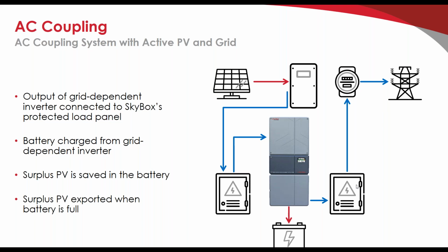Aaron asks, how many SkyBoxes can be connected? Is it possible to provide 100 amps of power to a critical loads panel? The short answer to the last part of your question, Aaron, is yes, it is possible. We're not recommending that people stack more than 2 SkyBoxes together today, unless they've done them already, are familiar with how the SkyBox installation goes, and have been trained on the SkyBox. Our technical support team is geared up to support 2 stacks of SkyBox.